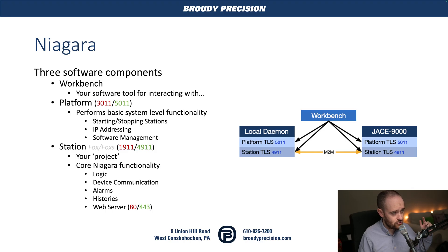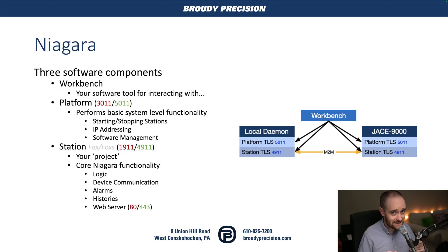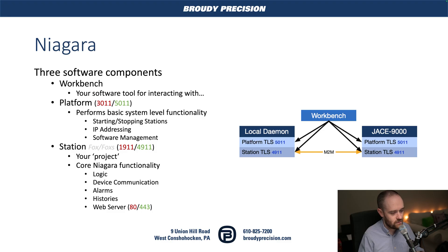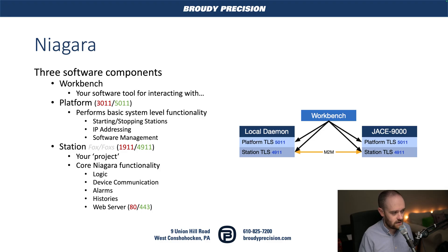The other two pieces of the Niagara picture are our platform and our station. The platform is sort of the 'Windows' of a Niagara environment — it handles basic system-level functionality like allowing you to start and stop stations, IP addressing, software management, and file system management. That's done directly on the platform across all platforms, so whether you're running Niagara on your local computer, a virtual machine in the cloud, or on a Jace, they all have a platform that looks and feels the same exact way, with only slight differences in what you can manage.